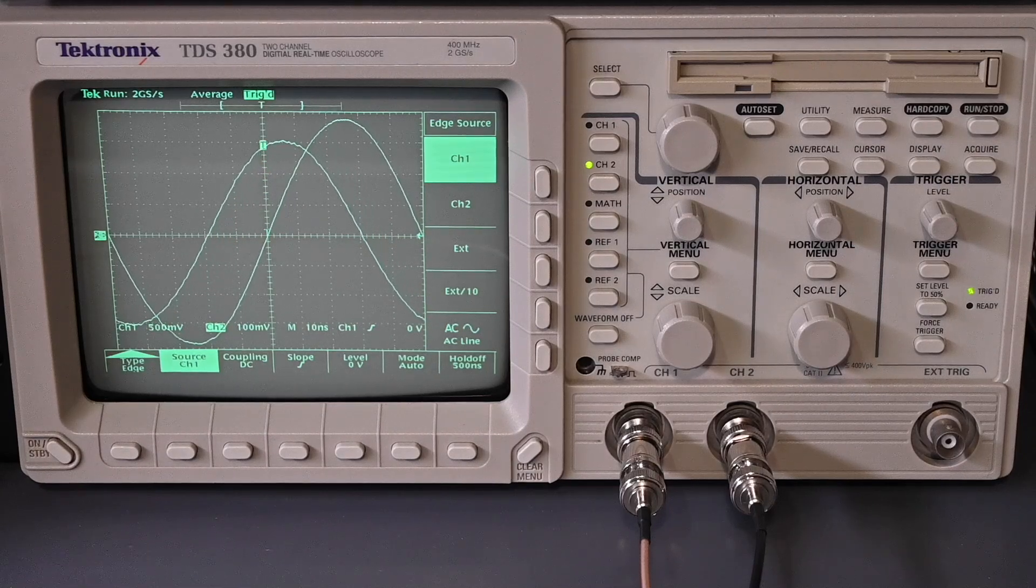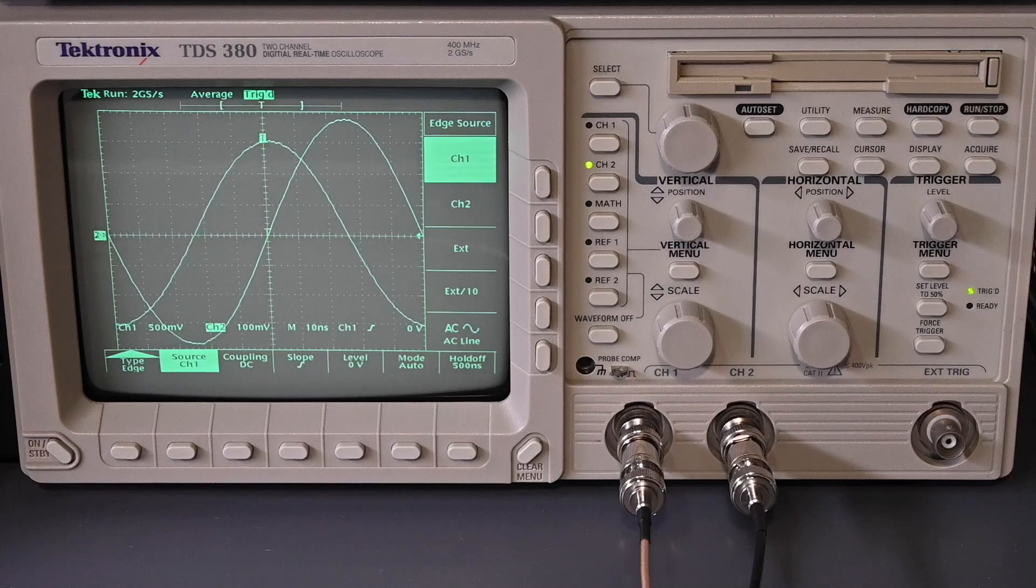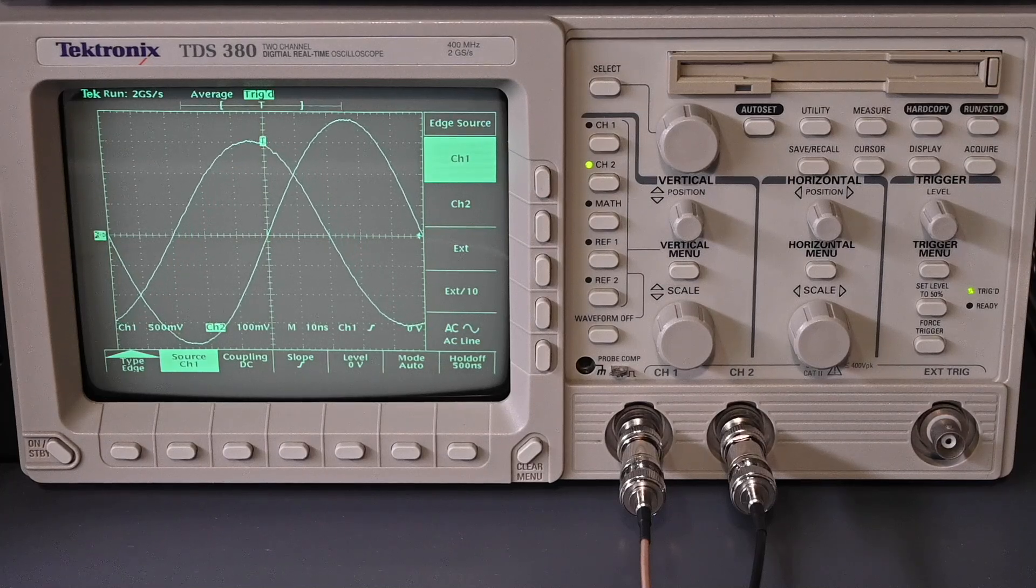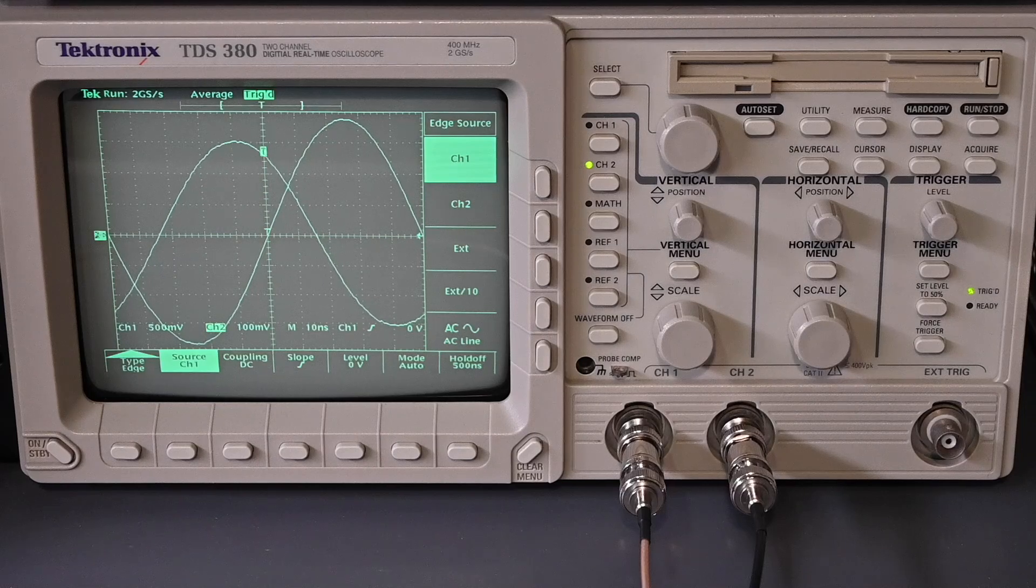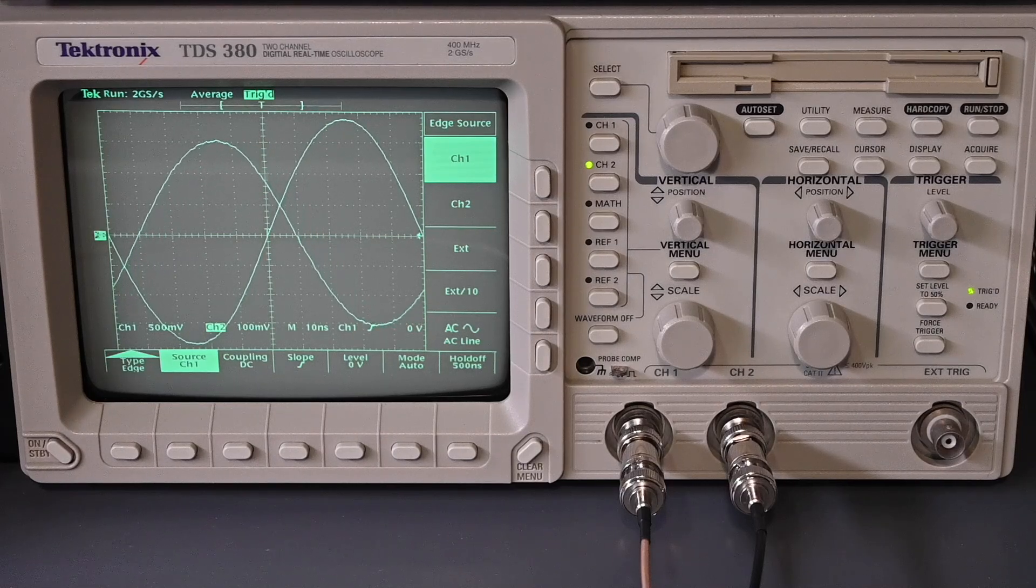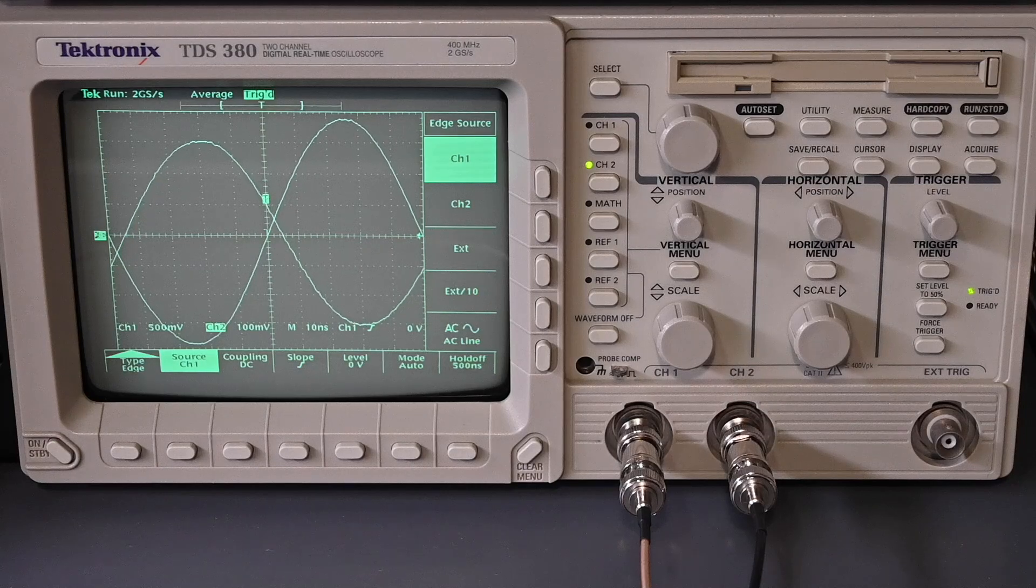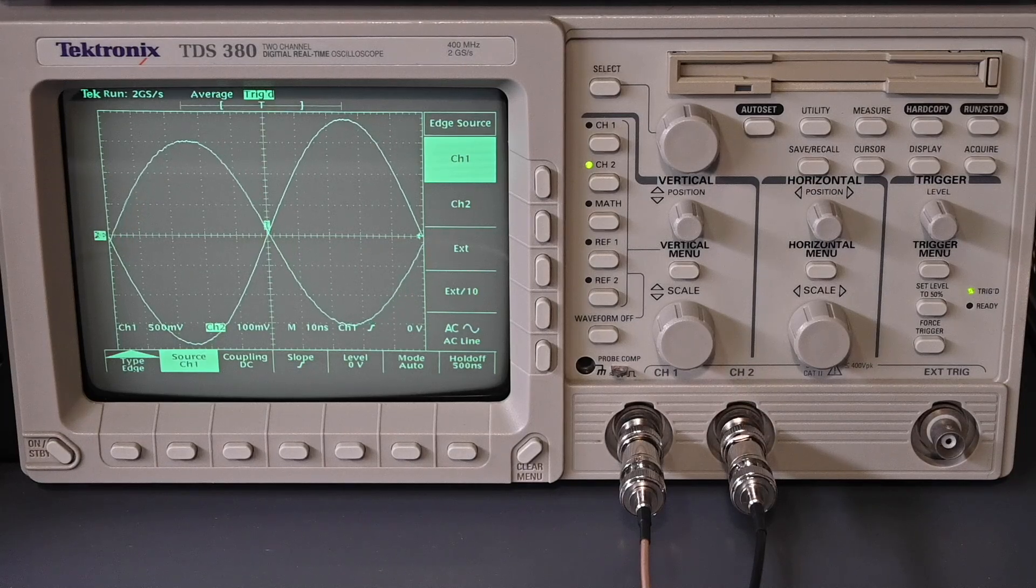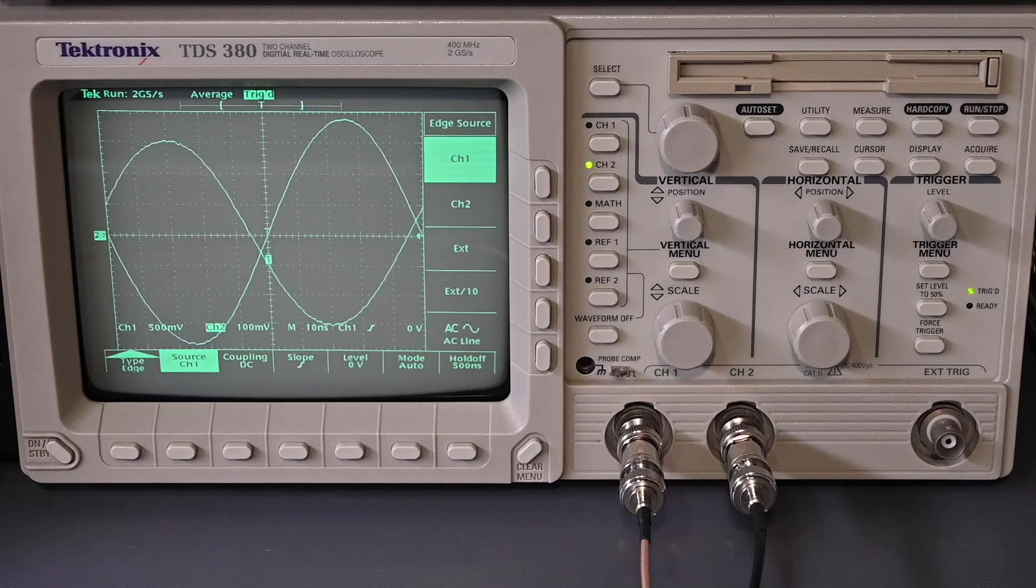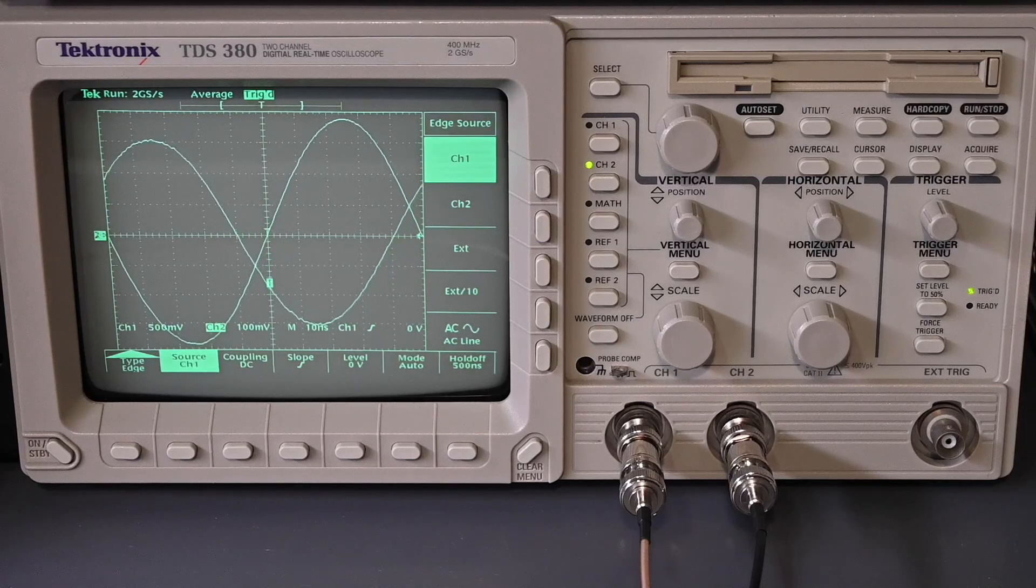And with the signal generator having such precise control on the output, down to just 10 millihertz steps, that kind of resolution is basically pointless if the time base oscillator is drifting and not exactly where it's supposed to be, because then the displayed frequency on the signal generator isn't really what's coming out of the signal generator.